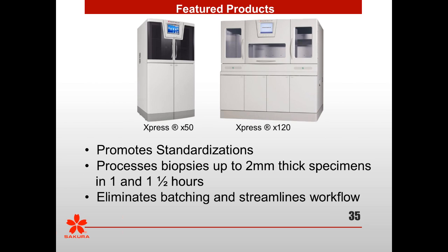The question states, you said all tissues can be rapidly processed. Does that mean I can put a nickel-sized piece of lymphoma to be processed to your specifications and it will be perfectly fine? Ooh, that perfectly fine is a very wide variety.